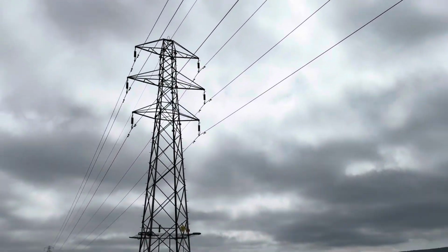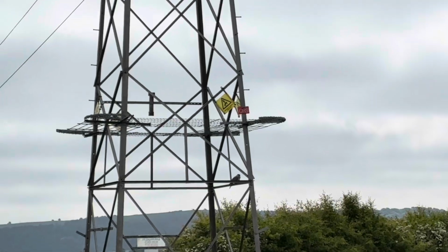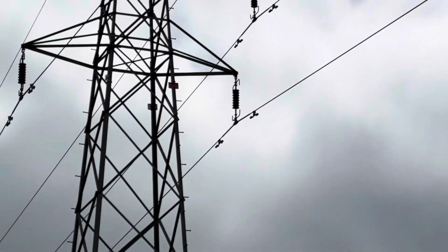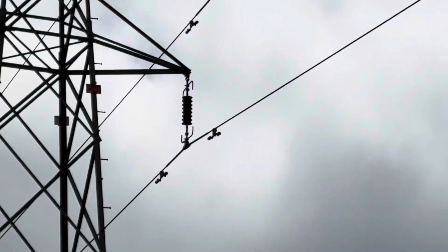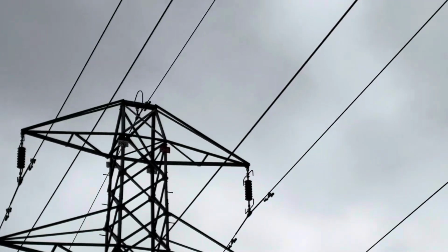And here I am just giving you guys a quick shot. There's some overhead line conductors. This is a PL-16 type tower, and we're just having a look right now to verify it's the right tower, the right site. You know, you can't always rely on as-built information. It's always good to get close and personal and verify circuit IDs and tower number plates and all that good stuff.